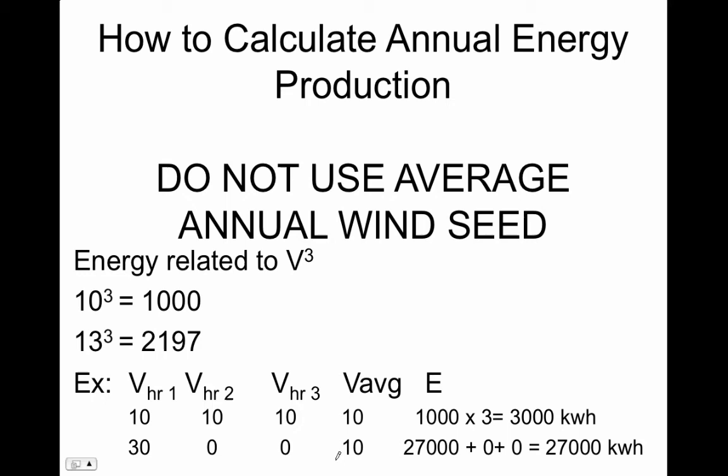The average wind speed can be very confusing. Look at the difference: 10 cubed is 1,000, but a 13 mile per hour wind gives 13 cubed equals 2,197 — just three miles per hour difference in wind speed gives you about twice the power output. So you can't use the average annual wind speed, multiply by how much power the turbine puts out at that speed, and multiply by the hours in a year. That's not going to work.